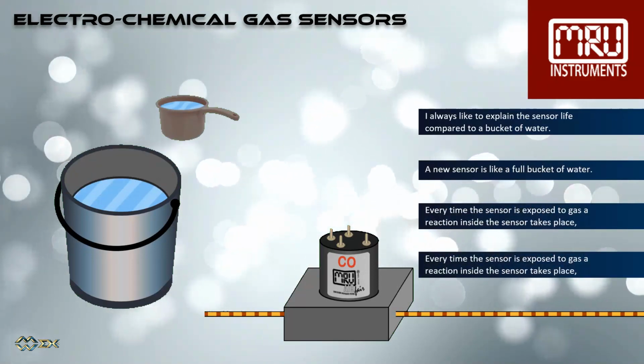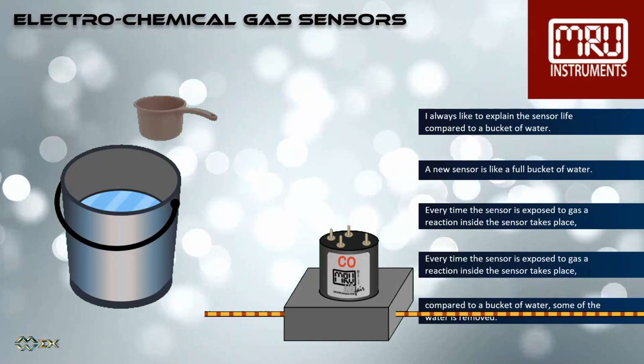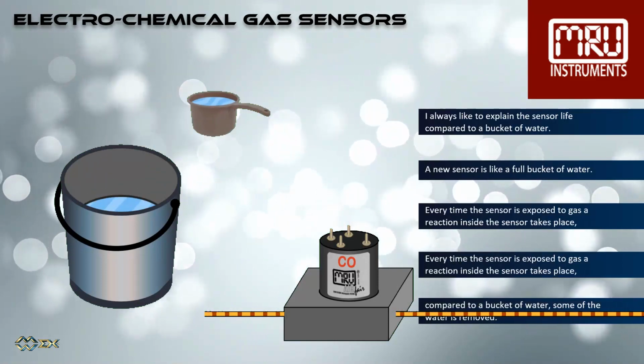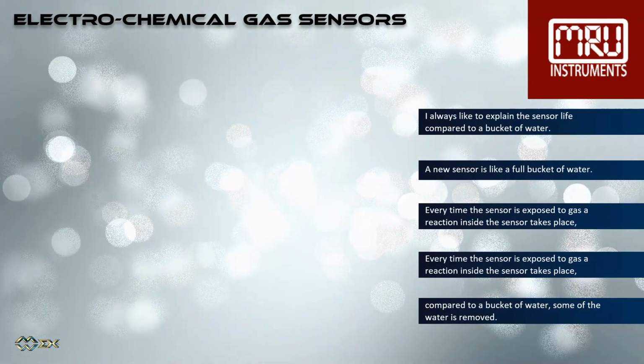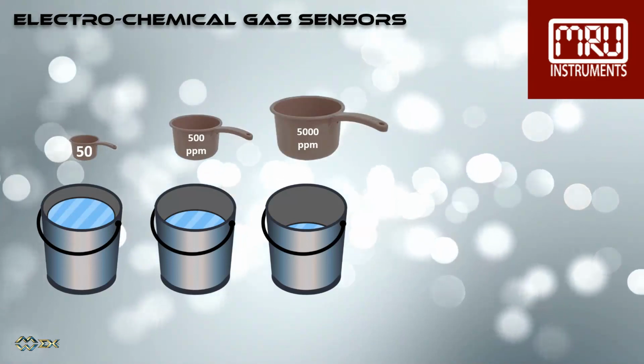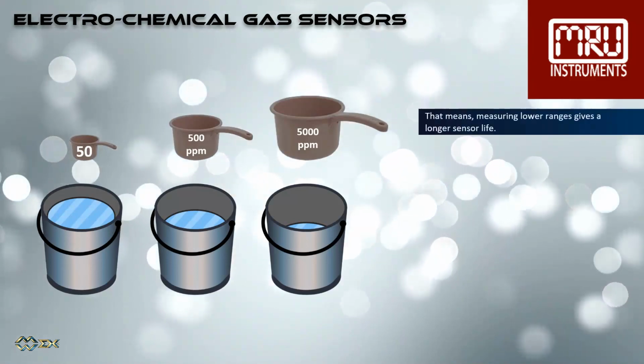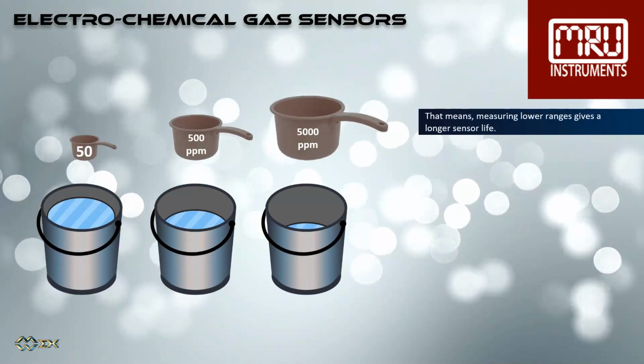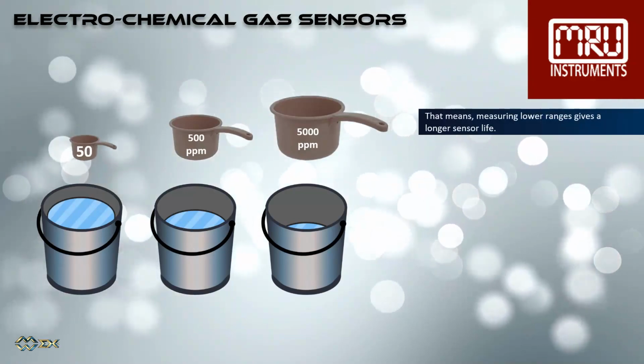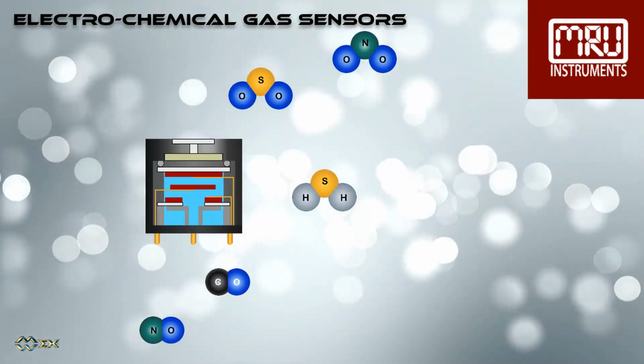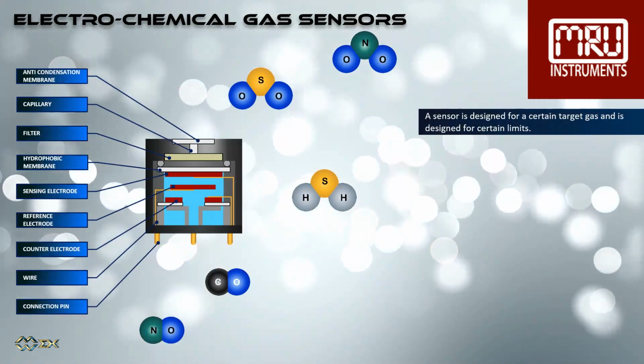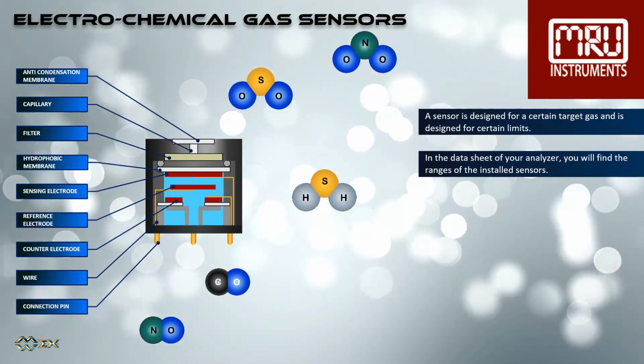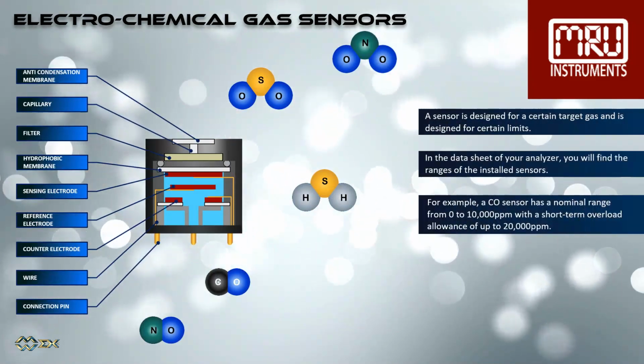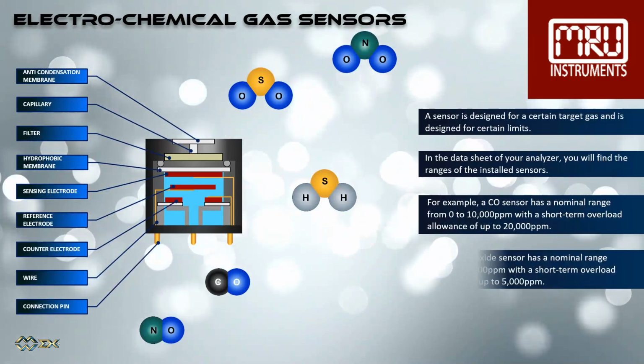Every time the sensor is exposed to gas, a reaction inside the sensor takes place. Compared to a bucket of water, some of the water is removed. The higher the gas concentration, the more water is removed. That means measuring lower ranges gives a longer sensor life. A sensor is designed for a certain target gas and is designed for certain limits. In the data sheet of your analyzer, you will find the ranges of the installed sensors.